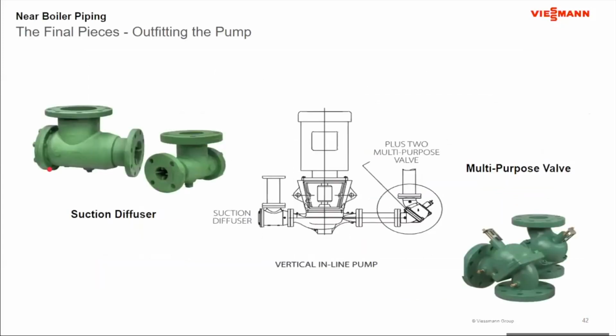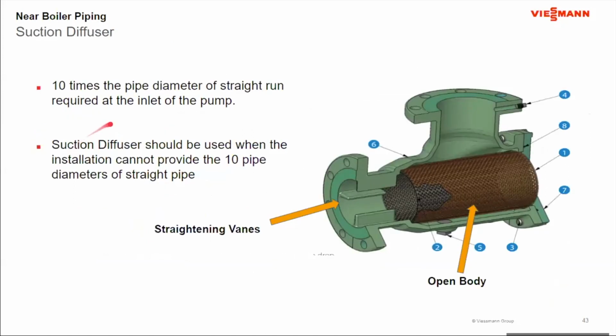Okay. Now, to finish out the system, a couple more things have to come into play. We've got to make sure that the pump is also properly outfitted. And again, I don't see these always showing up in the drawings, but I like to mention them because they should be there. Suction diffusers and multi-purpose valves. Let's start with the suction diffusers. Now, for proper pump operation, I should have 10 times the pipe diameter of straight run coming into the inlet of the pump. That allows the flow to turn laminar to reduce the turbulence on the inlet of that pump so it can operate properly.